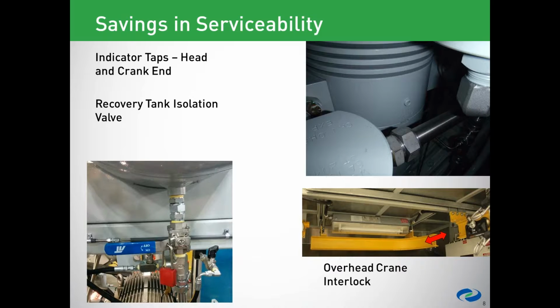And then one of the most exciting aspects is this overhead crane shown on the bottom right hand of your screen. The two yellow sections shown there are the crane. These two sections lock together or can be decoupled in order to get almost complete access to all of the major components for service as needed. This crane can be used to, for example, remove the main motor sheave, the compressor sheave, the fan motors, etc., and is really helpful with removing those components and taking them to the edge of the skid.